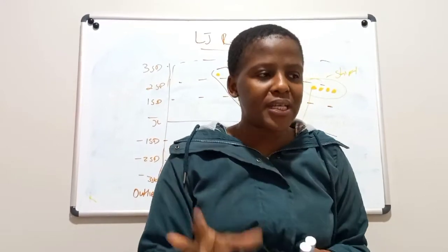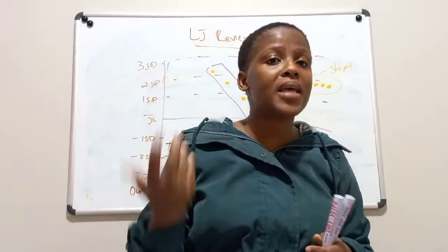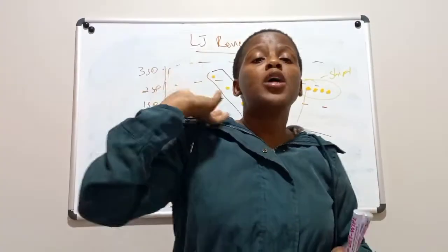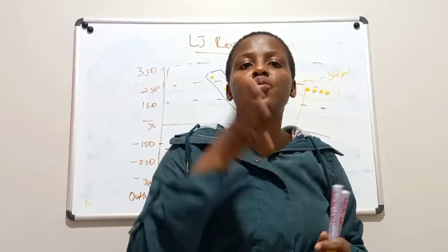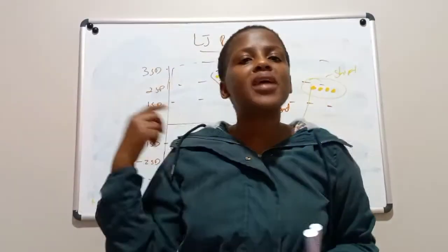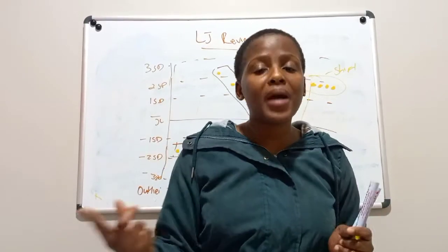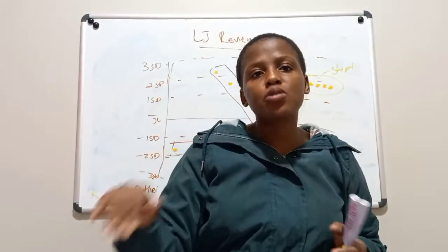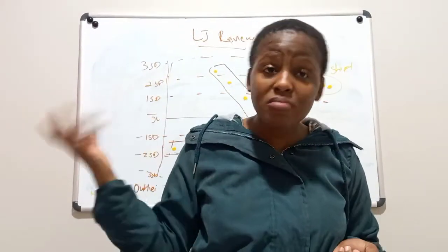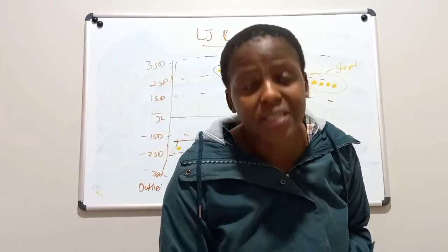I remember a story about the integrity of the calibrator. There was once a laboratory where I was working, where insulin constantly gave us a negative bias. So this issue was handed over to the application specialist from the supplier. When the application specialist came in, what he found out is that we were storing our insulin calibrator in the fridge, when it's supposed to be in the freezer. So every time, the stability of the calibrator was already compromised. Every time we were calibrating using a compromised calibrator, it caused our points to always be on the negative bias. And according to Westgard, if we have a 10x rule, if you can still remember from the Westgard rules, it's a rejection, especially if it's outside the 2SD point.